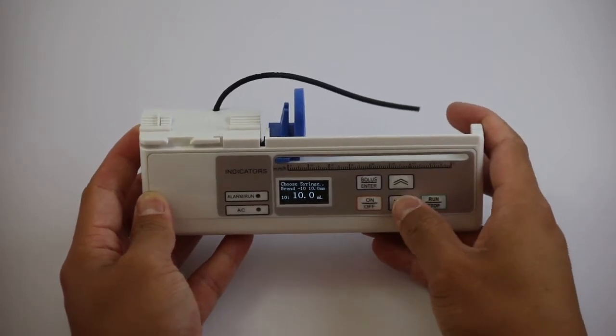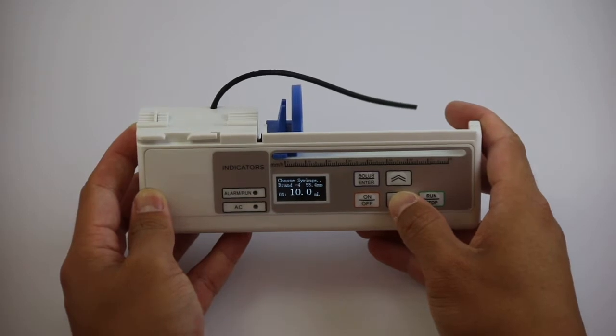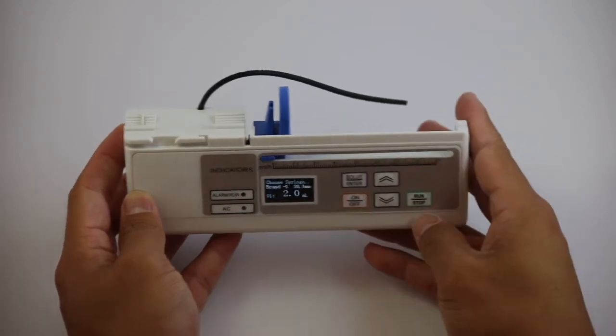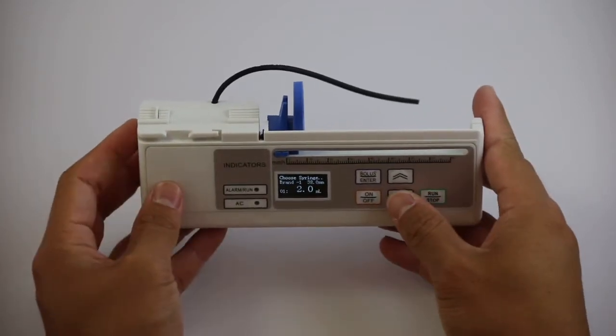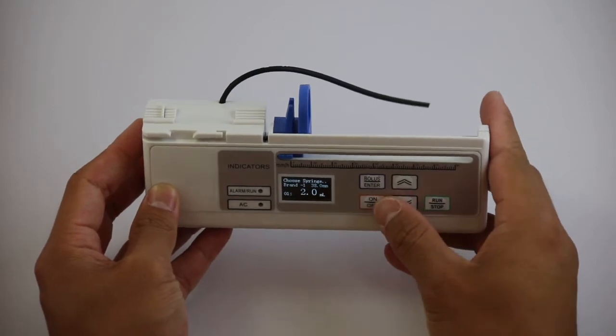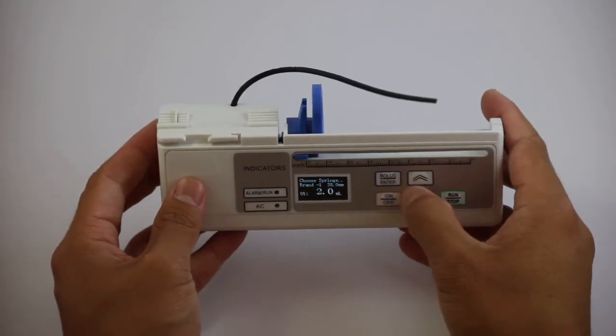As you can see, here are the ten different syringe slots that can be modified. Click the up and down arrows to select the syringe that you wish to calibrate. Click enter to set the syringe effective length.